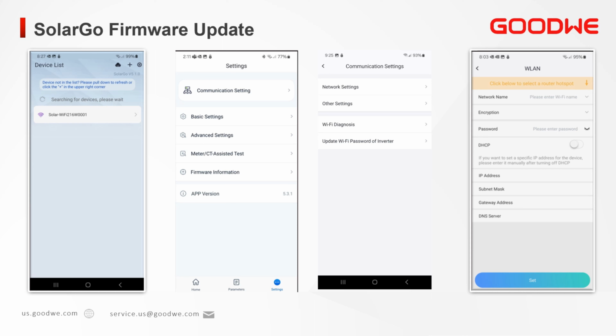Lastly, you will need to connect the inverter to the home internet. The reason for leaving it to the last step is that the inverter will automatically look for a firmware update available and will start the update. Ideally, you have completed all of the other steps of the commissioning and you are not required to wait for the firmware update. From the settings, click on Communication Settings and then Network Settings. Click on the network name and enter your customer's password.